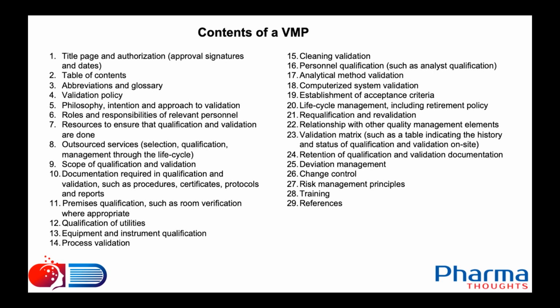If there is a change in the validated state, then when shall the process or method be requalified or revalidated, the criteria also should be mentioned. And relationship with other quality management elements such as risk assessment and all those things should be mentioned. A validation matrix, such as a table indicating the history and status of qualification and validation on site. Typically it can be available in the form of a schedule. We will discuss that. Retention of qualification and validation documentation. How much time, how much period shall the qualification and validation documentation be retained, shall be discussed.